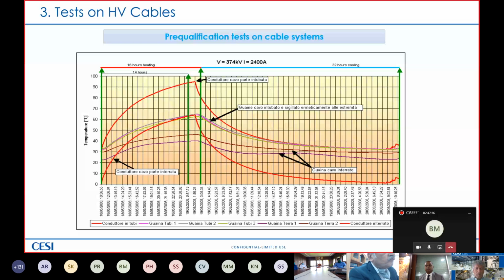I put here an example of a temperature of cable, a diagram of the temperature during a pre-qualification test. You can see that there are different colors. The lower ones are related to laying situations whenever you do not have a so-called hotspot. Normally, the hotspot is in the pipeline. Why? Because, of course, the pipe is a small one compared to the dissipation you can have in the earth or in a tunnel. So the highest temperature value is reached in the pipeline area.